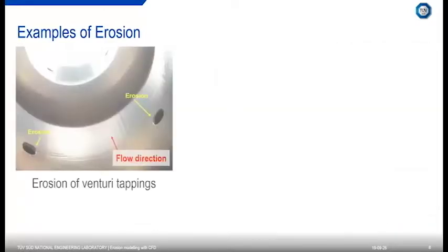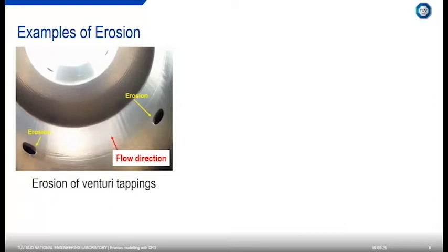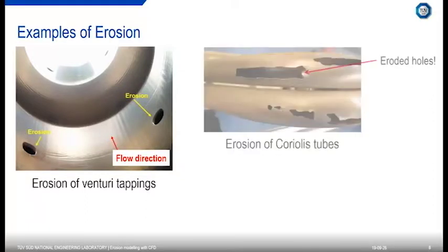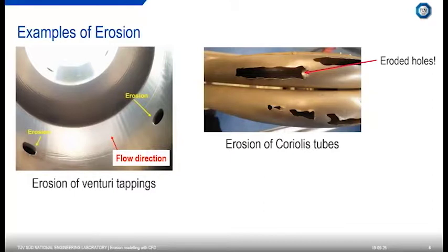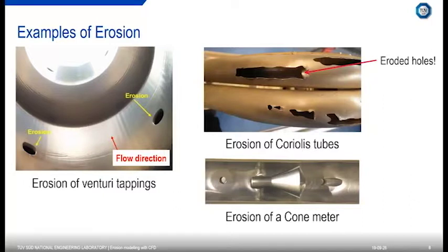Flow metres can also be subject to erosion. Here we have an example of a venturi, with the flow coming through the screen, and we have some erosion happening on the actual tappings. Another example is Coriolis tubes — this has become significantly eroded, similar to the pipe bend, and has actually punctured a hole through both of the tubes. And finally, a cone metre, cut in half so you can see the inside of the pipe plus the cone metre, showing rows of damage especially at the tappings.